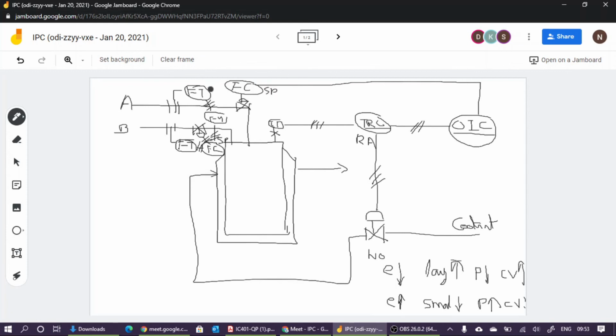So what is the measurement? This FT output. The current feed A flow rate is the measurement. So this one is the measurement. And this OIC output is acting as the set point of FC. Means if this one is within the normal region, if this control valve opening is within the normal range, then this OIC is giving a large signal. Okay, so this set point is large.